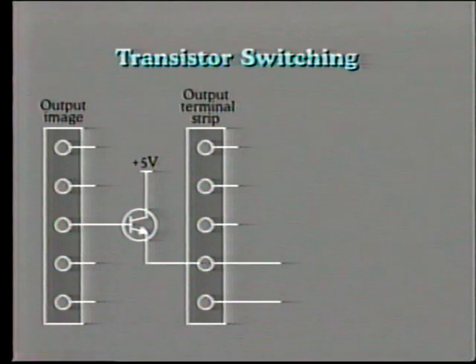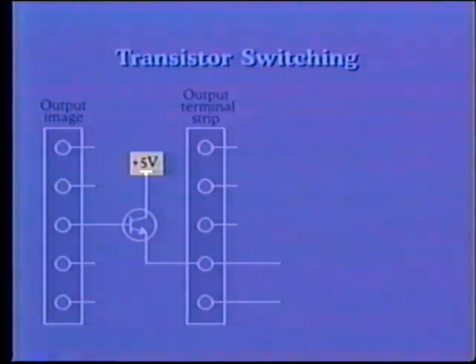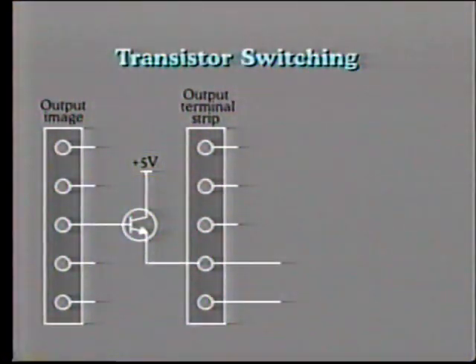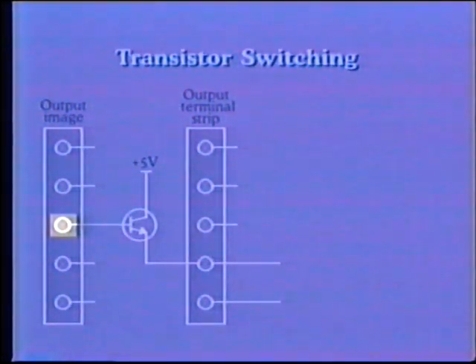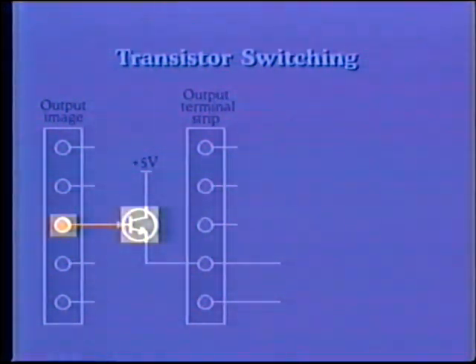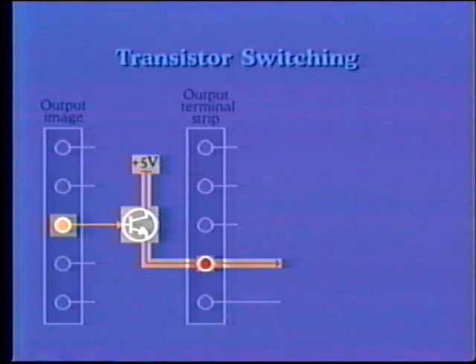In order to decrease the response time, transistor switching is often used instead of the electromechanical relay. This diagram shows one arrangement. The switching transistor operates on the internal 5-volt DC supply. When the output from the image memory is on, it triggers the transistor, and this applies the 5-volt DC to the output terminal. The switching capability of a light-duty transistor is typically limited to about 25 milliamps.